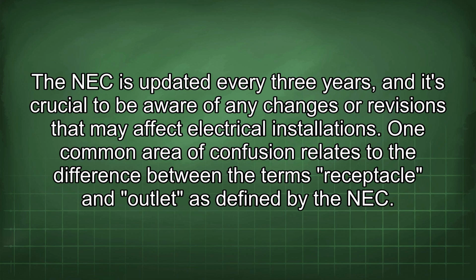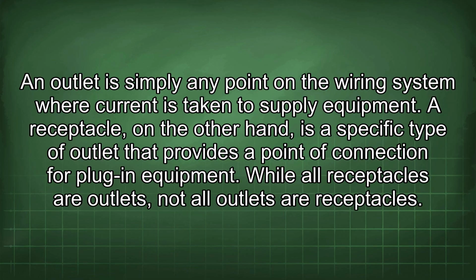One common area of confusion relates to the difference between the terms receptacle and outlet as defined by the NEC. An outlet is simply any point in the wiring system where current is taken to supply equipment. A receptacle, on the other hand, is a specific type of outlet that provides a point of connection for plug-in equipment. While all receptacles are outlets, not all outlets are receptacles.